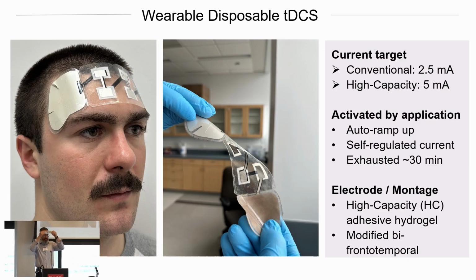So this would be wearable disposable tDCS. This is the actual device itself here. We don't need to make them transparent, but we just make them transparent so you can see the batteries inside. You can see the 4 batteries here. It's put on the head. It has an automatic ramp up, stimulation over a certain duration, and then a ramp down. So that's something we had to engineer. You can't have the sudden transients.